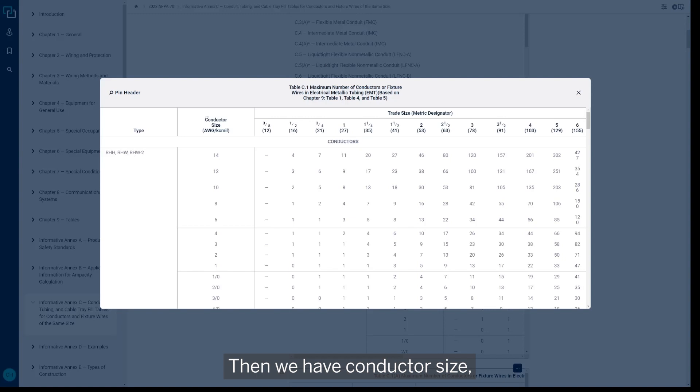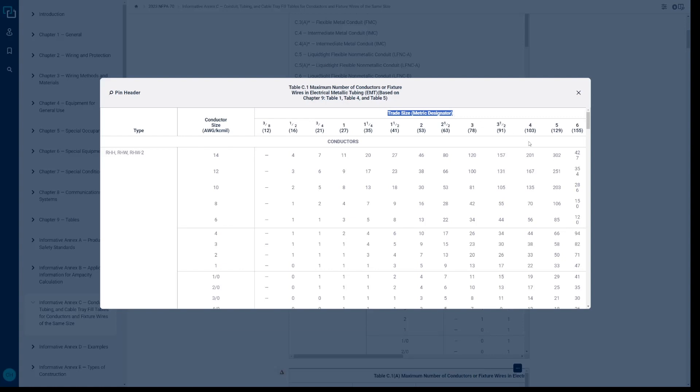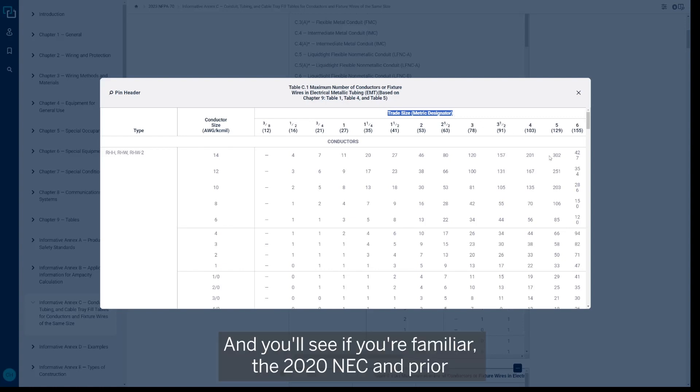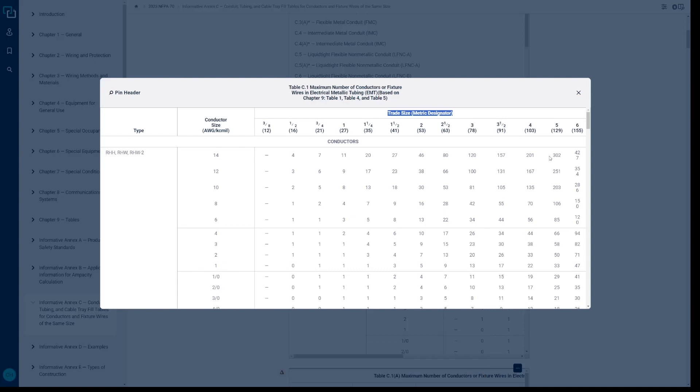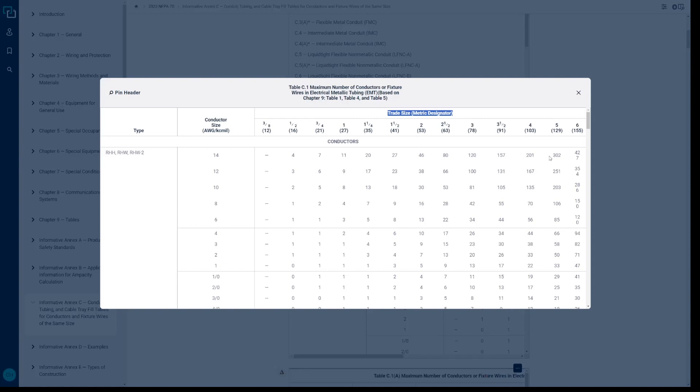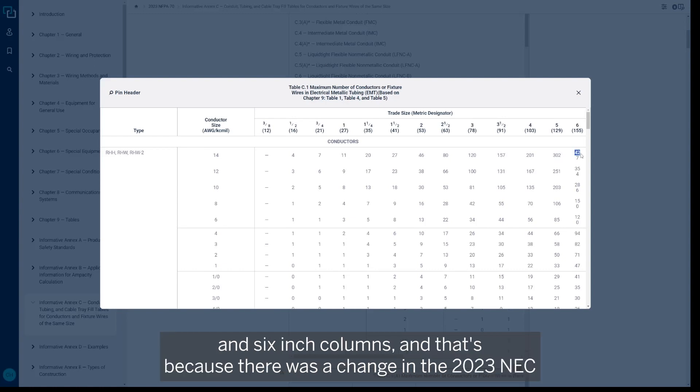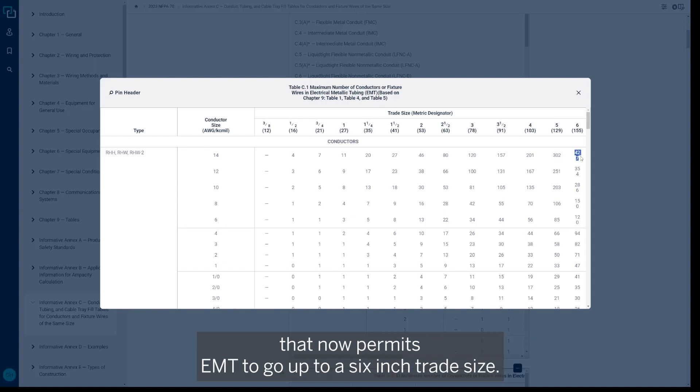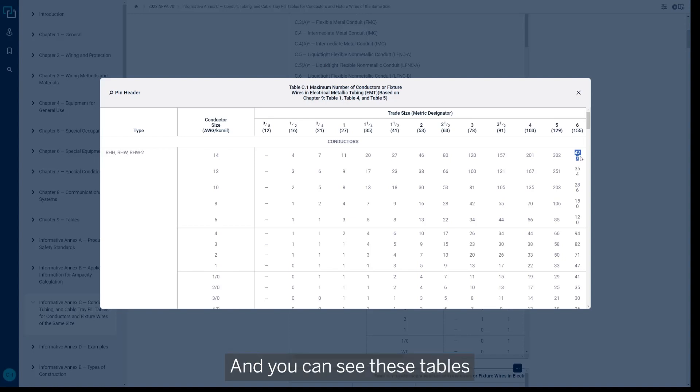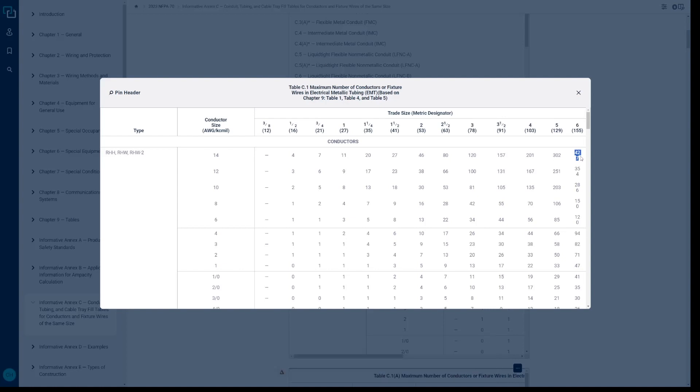Then we have conductor size, and then we go into the trade size of the conduits. And you'll see if you're familiar with the 2020 NEC and prior, EMT conduit was only permitted to go up to the size four inch. And now you can see over here we have values in the five and six inch columns, and that's because there was a change in the 2023 NEC that now permits EMT to go up to a six inch trade size. So that's a change, and you can see these tables have been modified to reflect that and incorporate those values.